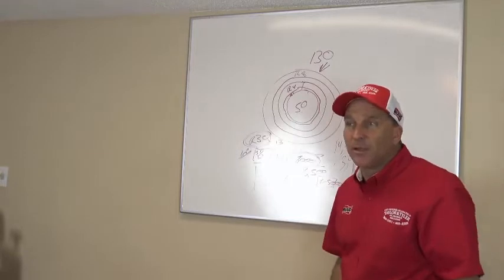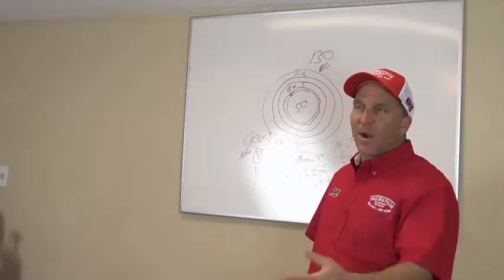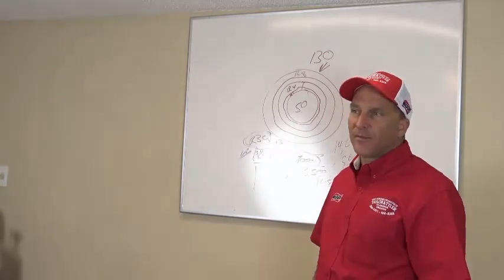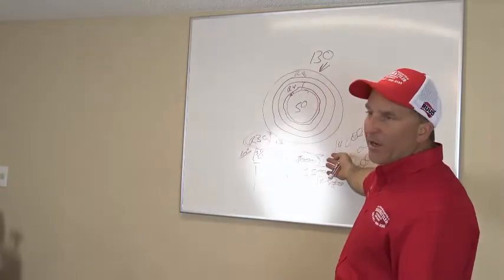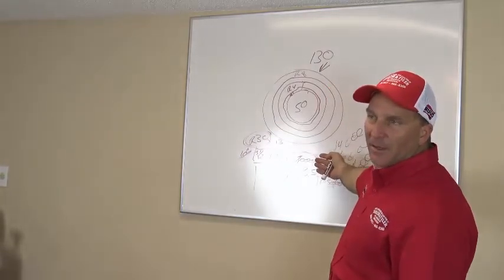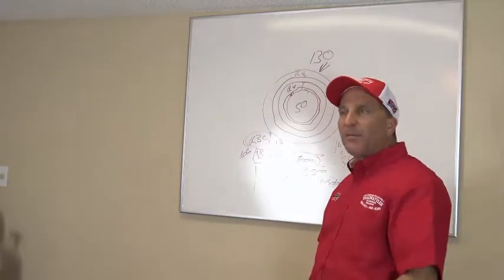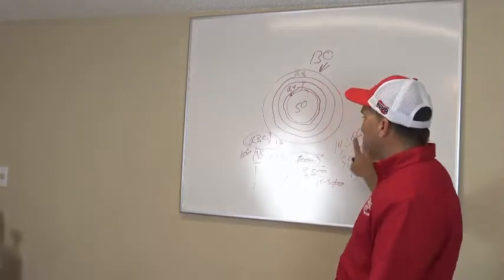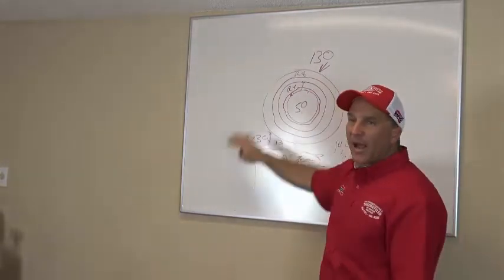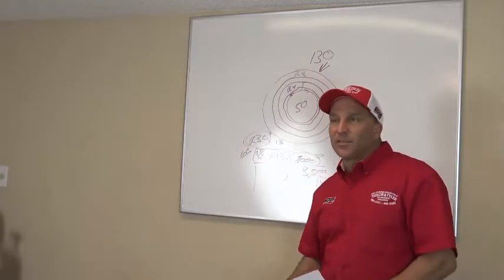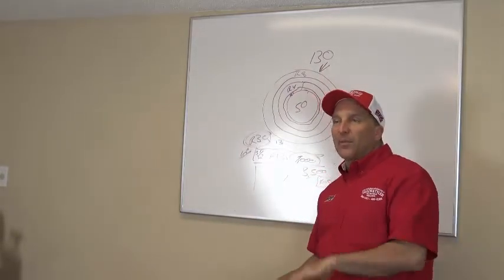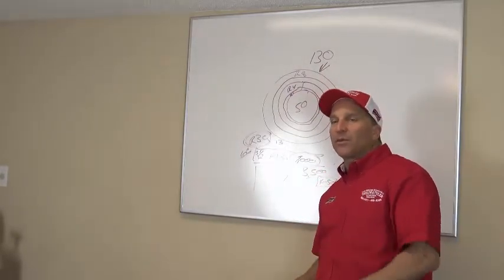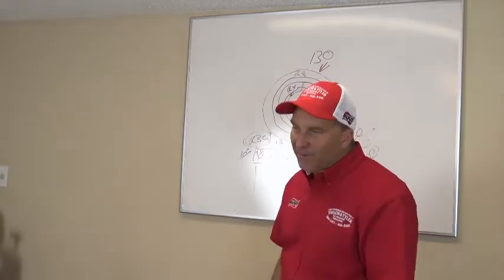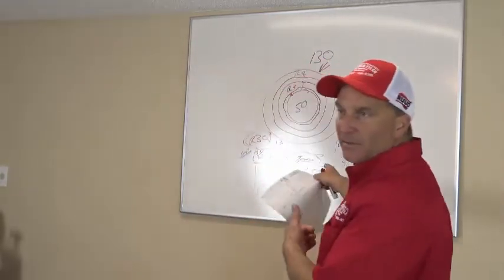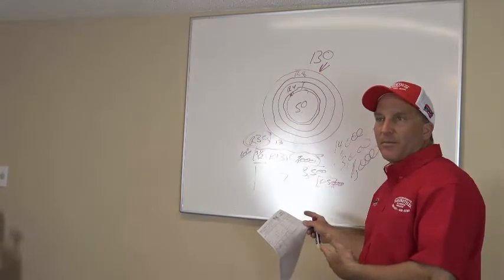You know what the customer's telling you when you're going to replace the system? Can you put a 4-ton in? Tell me why they want a 4-ton in their house. Because I'm throwing a ton of air conditioning out. How about if I put a 3-ton back in your house, man, and I insulate your ductwork, and I insulate your attic, and I put a 2-stage system in, and therefore 85% of the time I'm going to cool your whole house on a 1 3/4. Oh, my house never gets cooled. Of course it doesn't. Of course it doesn't.